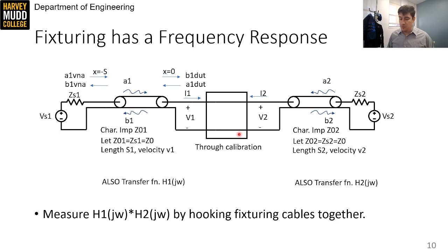Now, one detail of through calibrations is that it's very specific to the exact wires that you're using. Even screwing them in differently can change the values of a through calibration.